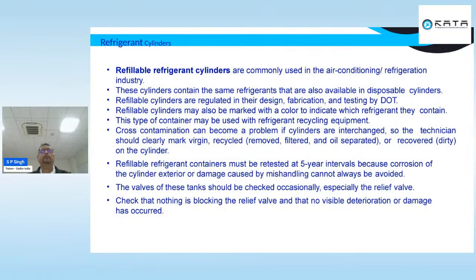While refilling the cylinder, the refilling of refrigerant must be taken care of, and we should gradually keep checking the cylinders, or use cylinders which have safety valves. There are cylinders available in the market with safety valves, so we should buy those cylinders too, so that it is not recycled - meaning once we have used a cylinder for R32, we shouldn't use it for R410. We should just buy separate cylinders and use each gradually for its own refrigerant.